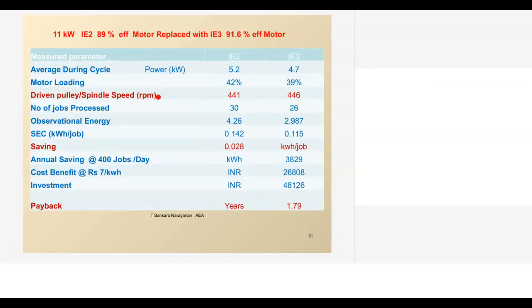Whenever we go for IE3, there is an increase in speed, mainly because in all high efficiency drives the slip is less. When the slip is less, RPM increases. That is what we have monitored here. Originally, the spindle speed was 441. Now it is 446. Spindle speed means after the motor and the gearbox. So this is the kind of speed variation. Then the energy was observed for certain operations. We found the specific energy originally and after the IE3 motor. For 400 jobs per day, installing the IE3 motor gives a payback of 1.79. This 1.79 can change if the number of jobs processed per day increases.